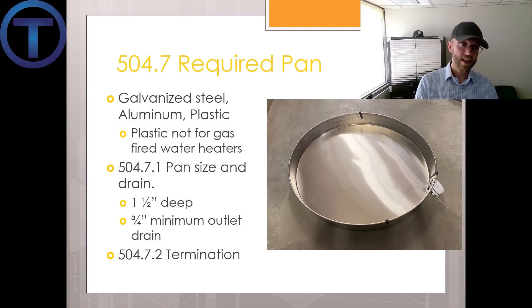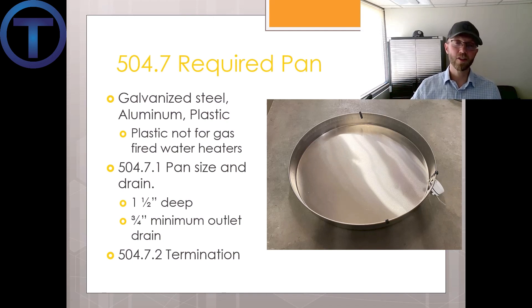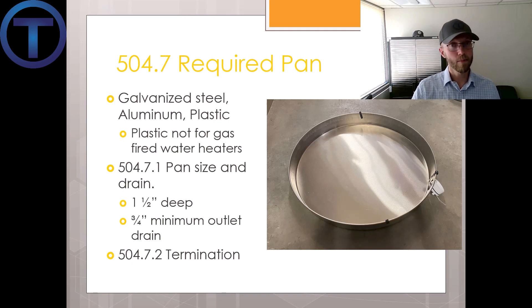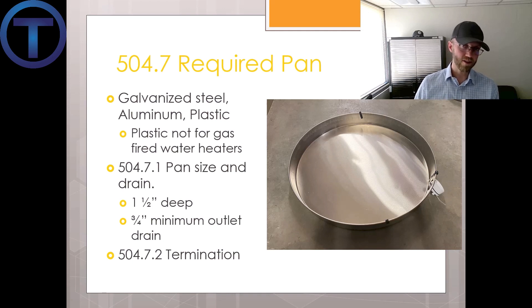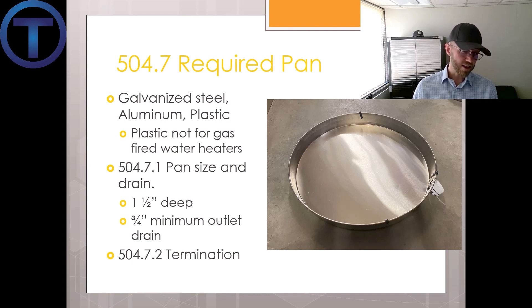Metal is required underneath a gas-fired water heater. The pan size and drain are specified in 504.7.1: the pan has to be a minimum of one and a half inches deep and must have a minimum three-quarter inch drain outlet. 504.7.2 talks about the termination point for the pan drain — the pan drain shall extend full size and terminate over a suitably located indirect waste, and terminate not less than six inches and not more than 24 inches above the adjacent ground surface if discharged outside.